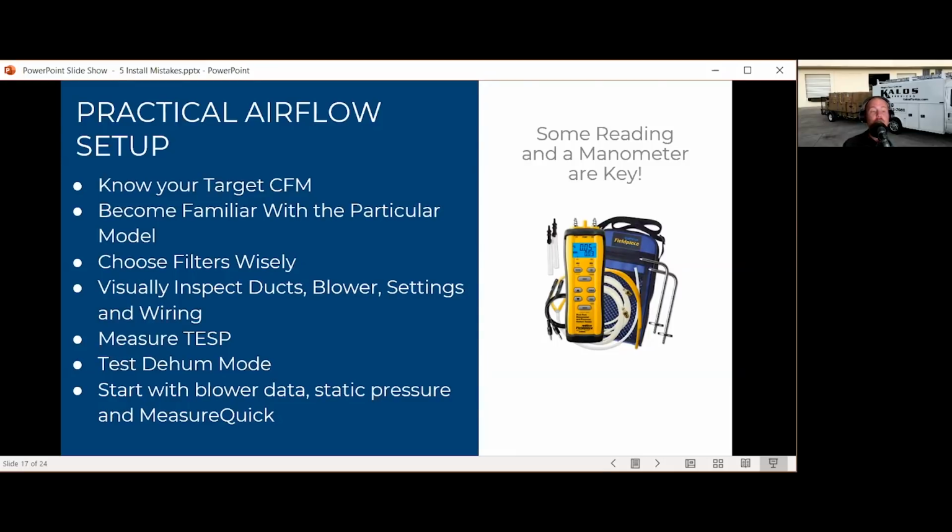That means that if you attach that thing to ductwork or filters or any other external pieces, and you are higher than that number, total external static measured once you're done, that doesn't necessarily mean the equipment's not going to work. Depending on how extreme it is, it may work and it may be on the chart of operation.